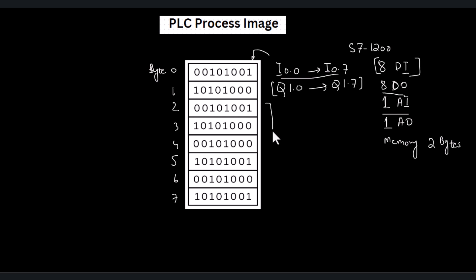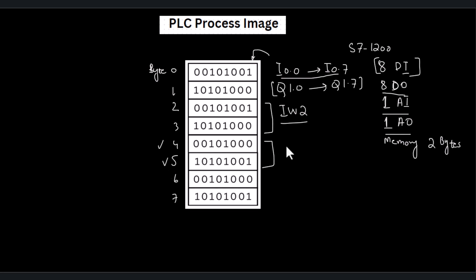Since we have one analog input channel, these two bytes addressed as IW2 are allocated for the data coming from the analog input channel. For the one analog output channel, bytes four and five are allocated — addressed as QW4, because the byte starts from four and ends at five. We address the analog input as IW2 because it starts from byte two.